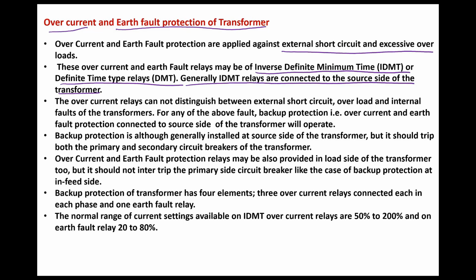Now the overcurrent relays that we are implementing here cannot distinguish whether the fault is inside the transformer or outside the transformer. So they will also act as a backup protection for the Buchholz relay and overflux relay. The overflux relay will only operate if the flux V by F ratio increases beyond a certain value. The Buchholz relay will operate when there is a slow developing fault inside the transformer.